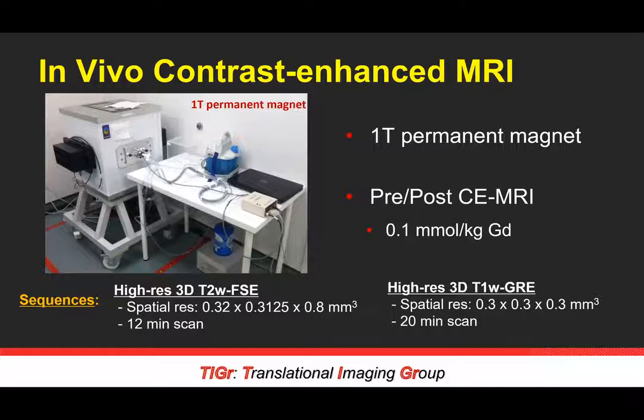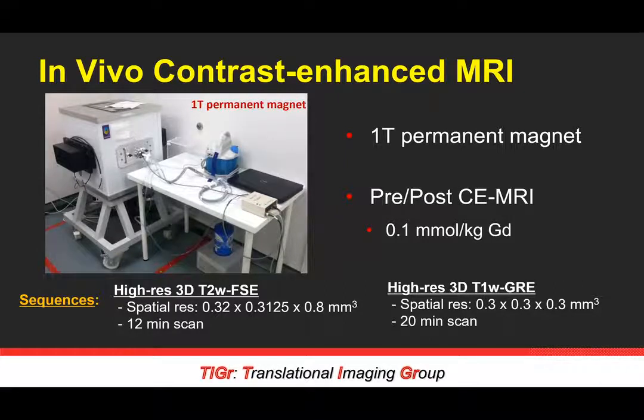We are using the 1 Tesla permanent magnet — the Aspect M2 — along with the Aspect M7 for higher resolution imaging. We use a 3D T2-weighted FSE sequence for standard anatomical imaging and a high-resolution 3D T1-weighted gradient recall echo sequence with 300 micron isotropic resolution. A big challenge in fetal imaging is that we can't just gate for maternal respiratory and cardiac motion — fetal motion must also be addressed by acquiring multiple averages and discarding those with excessive motion artifact. Our scan time encompasses five external averages for the gradient recall echo protocol.